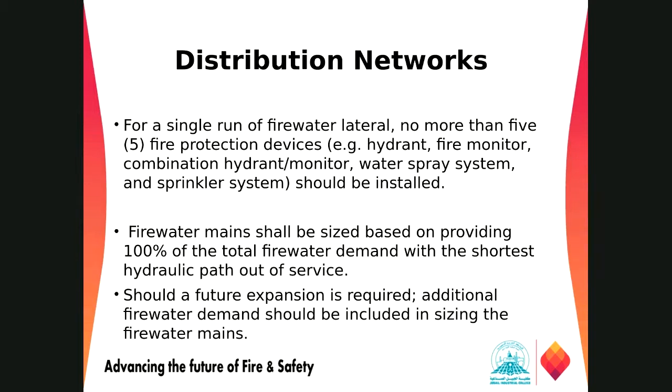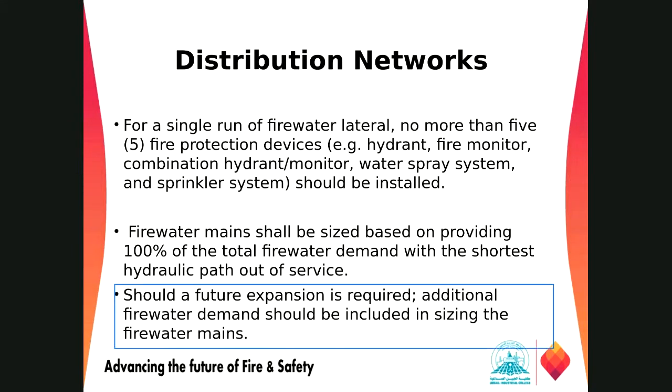One thing we always have to think about while designing any fire protection system for a new project is future expansion. If you know your plant is going to expand a lot in the future, we have to size your fire water network based on that, because you don't want to add another loop or another fire pump later. Also, if there is a future expansion, you may approach the engineering team or the management team to learn their plans, so that we can extend the same line for future use.